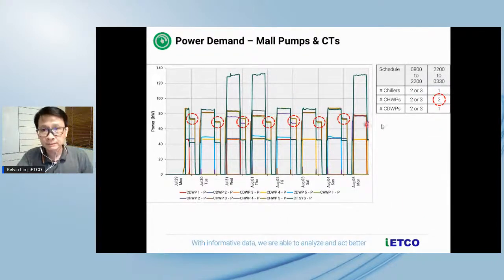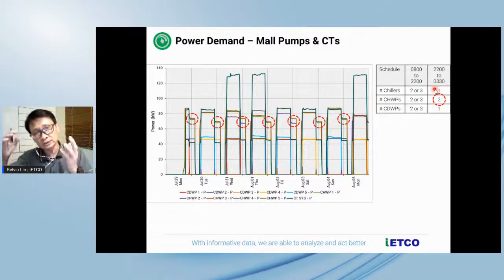For example, sometimes between 10 to 3:30 in the morning, you will see two chill water pumps running, but only 1 chiller running. So there are some issues with the control system in place. Without real-time monitoring and visibility, you are not able to capture such information, and without it you cannot continuously improve the building energy consumption to make it more efficient.